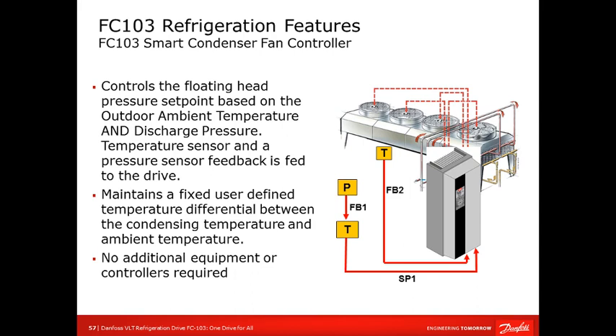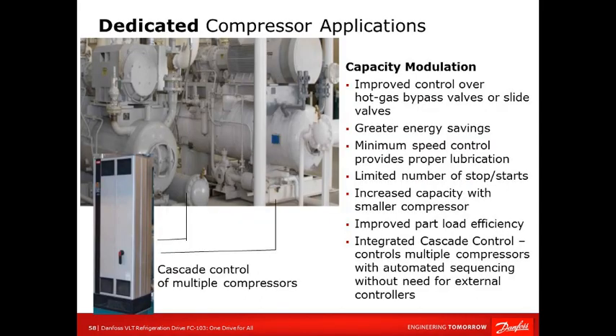For the smart condensing fan control, this is just something to share, again, when we're operating multiple fans in parallel. Here we're showing, from our design guide, that we're monitoring the head pressure and the discharge pressure, and the feedback is fed to the drive, and then the drive reacts depending on what the process is calling for. Here we're just trying to say the drive can be programmed to do a lot by itself without the use of a controller. So in some cases, if there's an expansion, to reduce cost or additional equipment, there is a lot of intelligence built into the drive. There's a built-in PID and other capabilities to reduce the overall cost. Again, it's just an option, and to make you aware that it's capable.